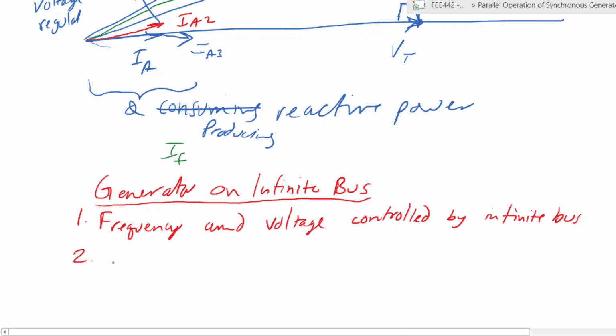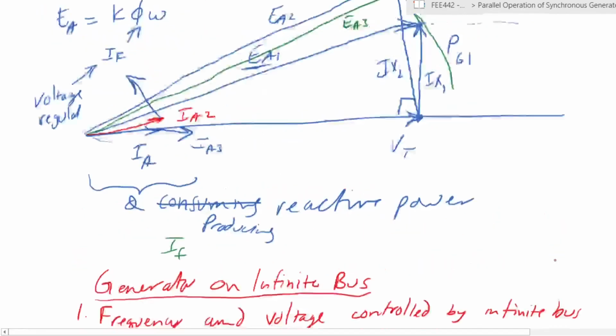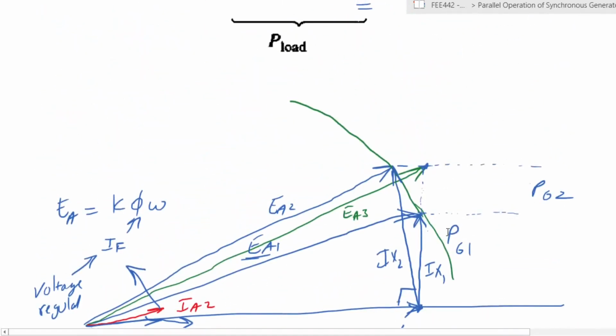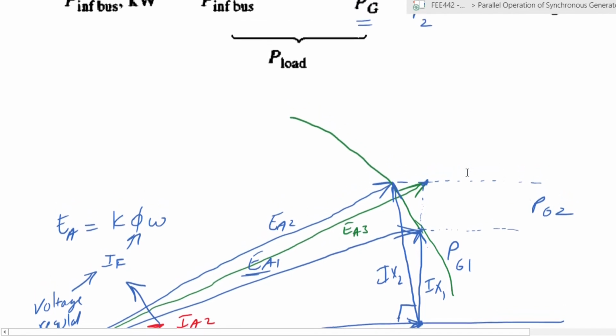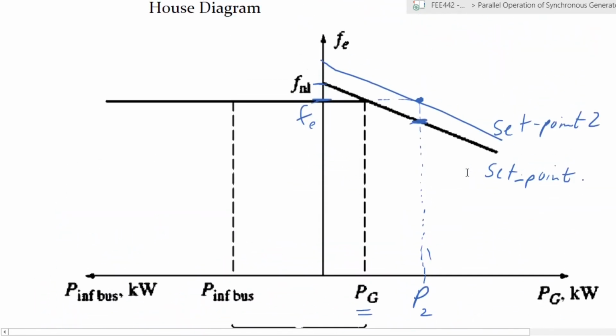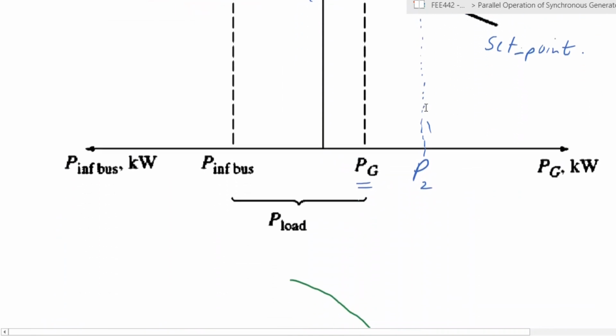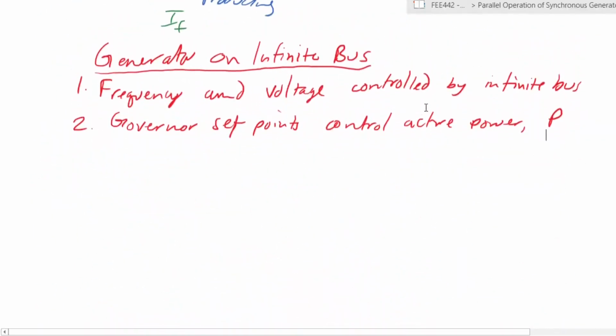Number two, the governor set points control active power. We've seen that already here. If you want to go from PG1 to PG2, you need to be able to change the value of the governor. You need to change the set points that you are applying.